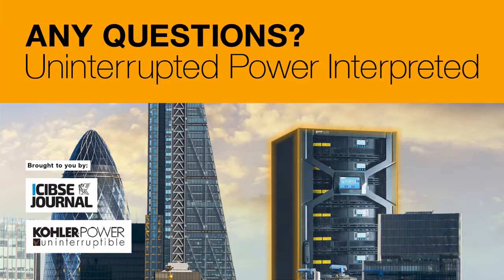Okay, one more question on the batteries, then we'll move on to other areas. Is there any guidance for those heat emissions from the UPS? And is that related to ratings, or is it purely down to manufacturer's data? Does it have to be done case by case? It's purely case by case. Obviously, a different UPS of a different size from a different manufacturer will have a different heat output. So a 10 kVA UPS compared with a 500 kVA will have a completely different heat output. But the manufacturer's specification should clearly state the heat output from the UPS.